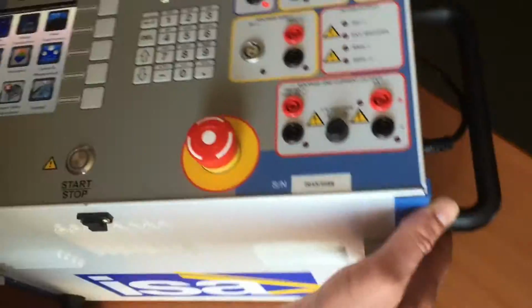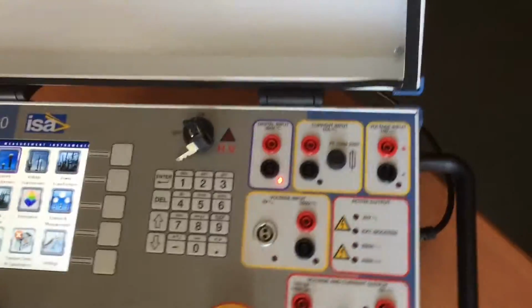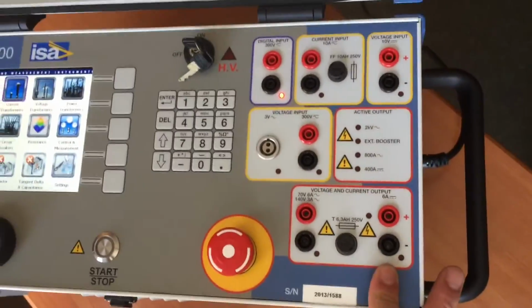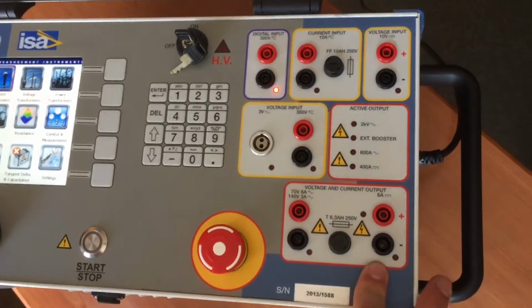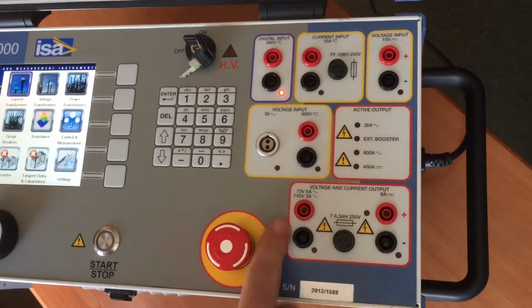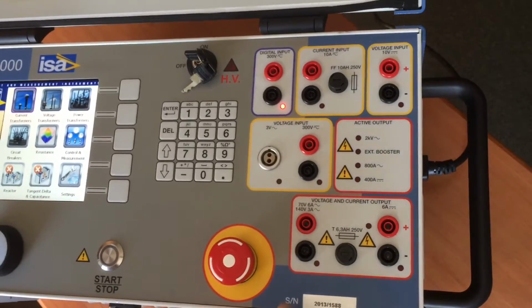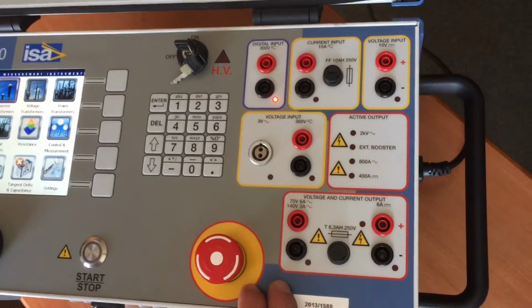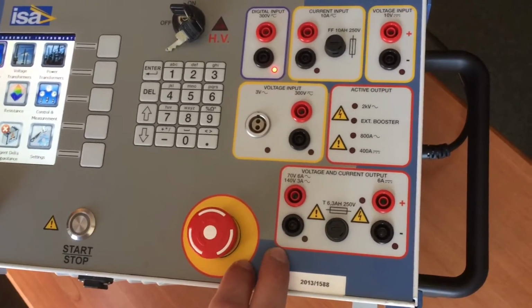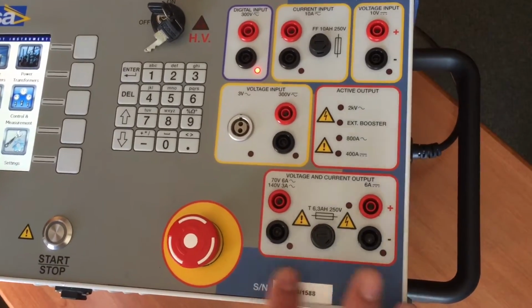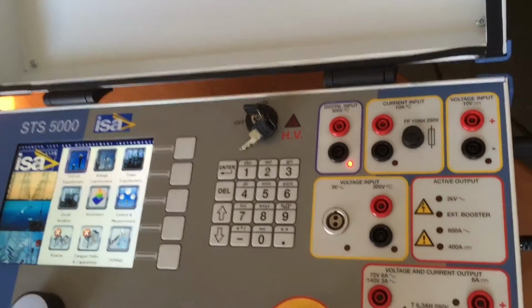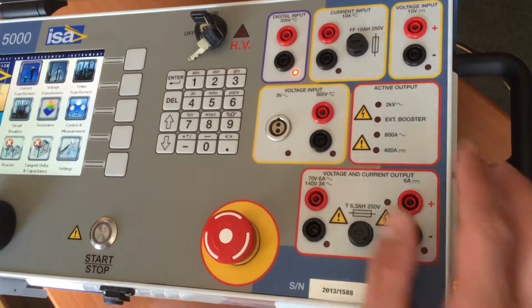In addition to that, we have the low current and low voltage outputs. So for example, the 6 amp DC output is used in testing of winding resistance, and the AC output can be used for many things. You can use them, for example, for the ratio of voltage or ratio of power transformers. So here we stop with the red frames. These are the red frames which signify the usage of the outputs we have just seen.